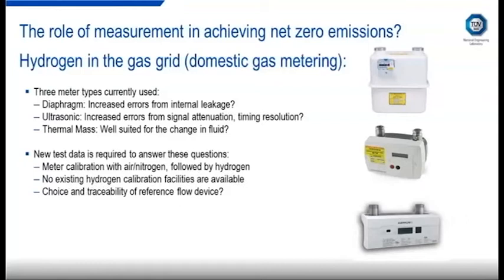So for diaphragm meters, we're concerned about the meters becoming overranged, but also increased slippage or internal leakage due to the fact that hydrogen has a smaller molecule size and a smaller density than the other gases. With ultrasonic meters, we're concerned about the change in acoustic properties. So the existing transducers are probably not suitable for this change in gas. And with thermal mass meters, assuming that the heating element and the sensing elements are appropriately spec'd for the fluid property ranges, then they could perform quite well with the pure fluids.